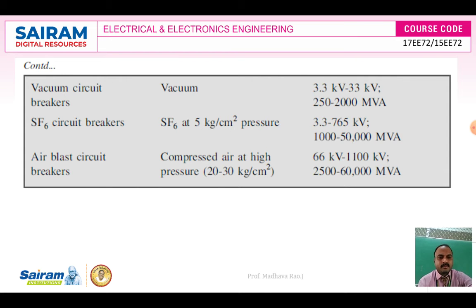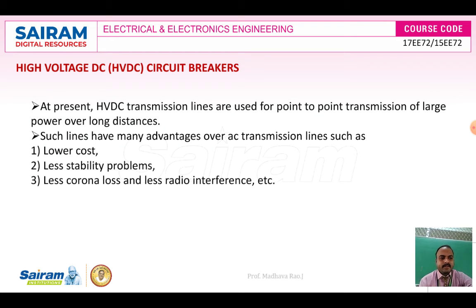And the HVDC circuit breaker. This is one of the circuit breakers. You can use it for DC transmission and DC distribution. We have different circuit breakers. The previous ones are air blast, air brake, oil, SF6 and vacuum. All these five types of circuit breakers we use for AC transmission and AC distribution. But the HVDC breaker we use only for HVDC transmission.